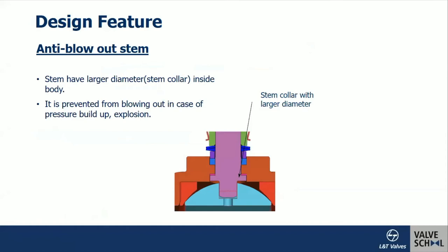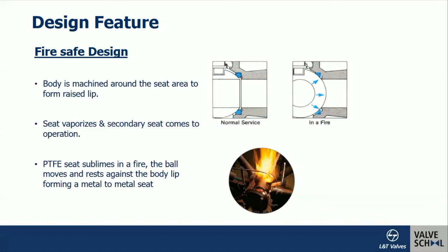To illustrate the fire-safe design: during normal service the soft seat (shown in blue) provides downstream sealing. If the soft seat gets sublimated or extinguished due to external fire, a raised lip provided on the body comes into contact with the ball, ensuring sealing and preventing further fluid flow. This provides effective sealing during a fire event, though the seals and seats must be replaced afterwards.